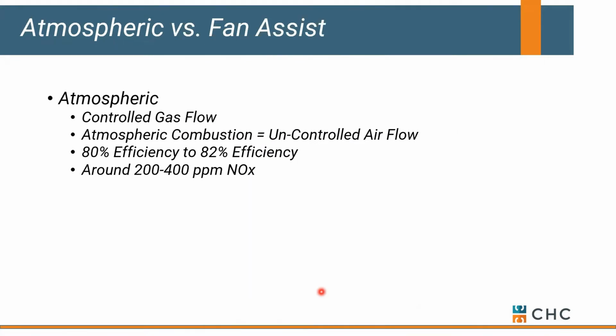One of them is efficiency. They're not terribly efficient, typically 80 to 82% if everything's clean and they're straight from the factory. The other big downside here is the emissions. As far as what they're sending out into the environment, they're not real friendly to our greenhouse gases. They're putting out NOx levels of 200 to 400 parts per million. So you're seeing a lot of air agencies and counties not allow atmospheric boilers anymore. First, because they're not efficient, and secondly, because they're not real clean or friendly to our environment.